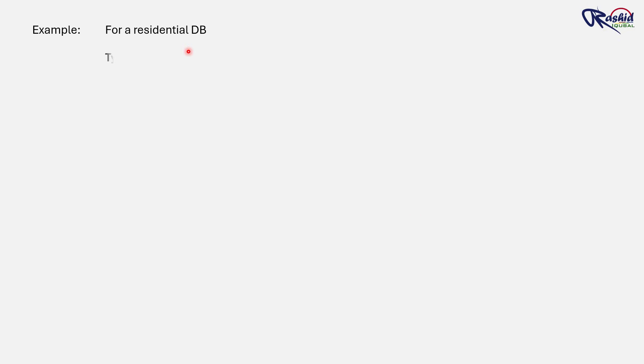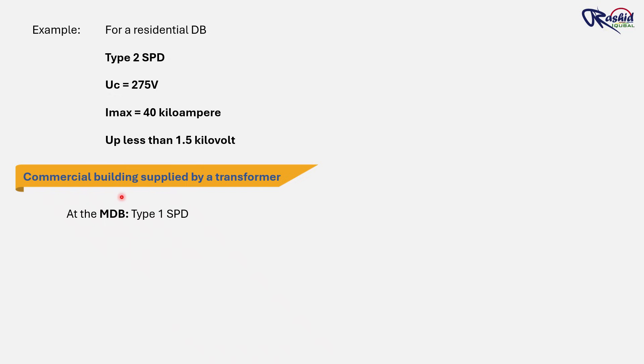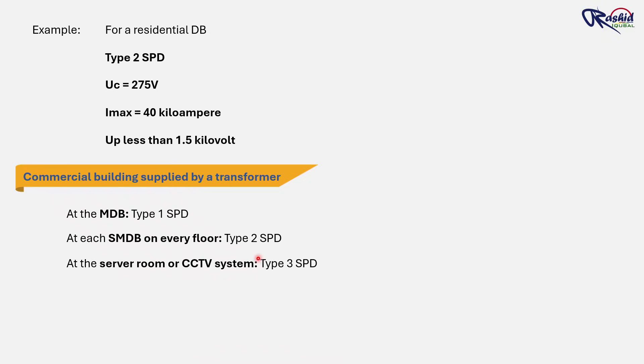SPD must be coordinated with the upstream breaker or fuse. For a residential DB, we usually select a Type 2 SPD with UC rating 275V, IMAX rating 40kA, and UP less than 1.5kV. For a commercial building supplied by a transformer: at the MDB, install Type 1 SPD to stop lightning surges directly from the sky; at each SMDB on every floor, install Type 2 SPD to stop switching surges; and at the server room or CCTV system, install Type 3 SPD to stop residual surges. This way the building is fully protected from any type of surge, whether from lightning or switching operations.